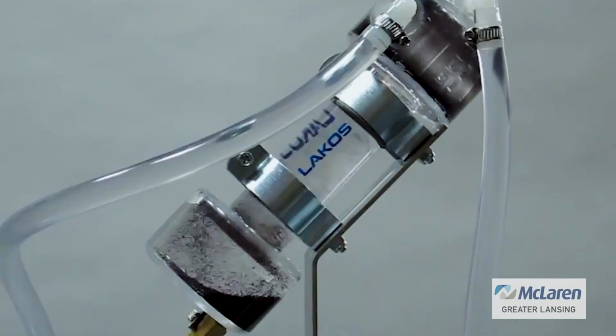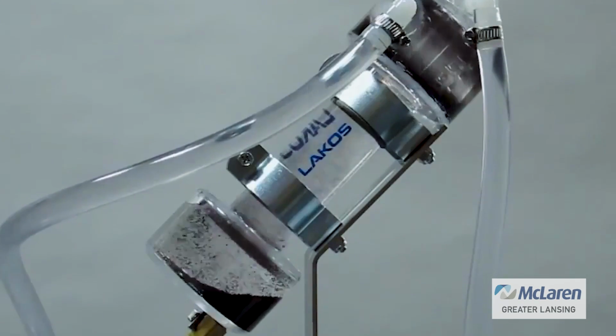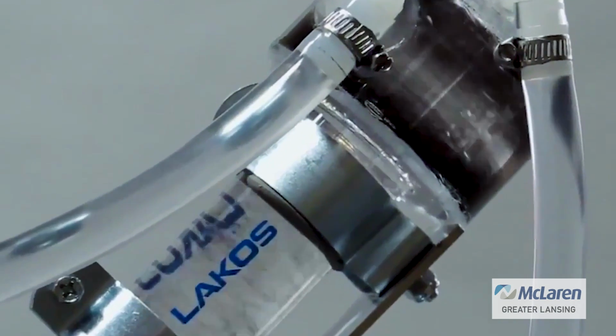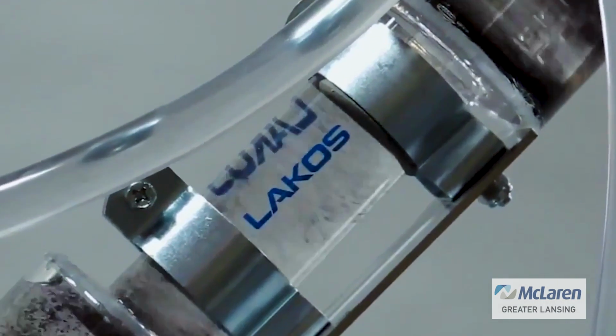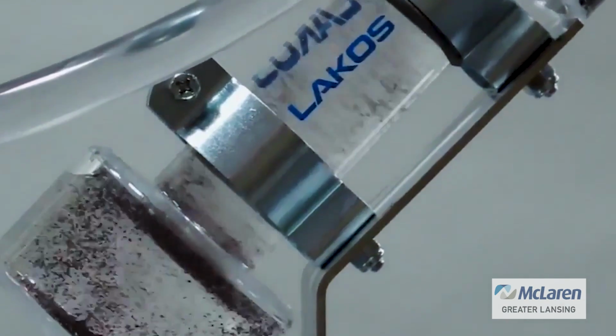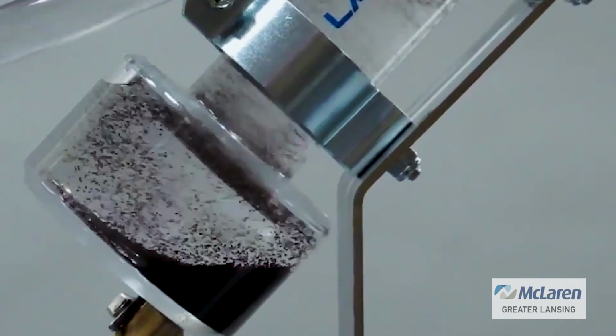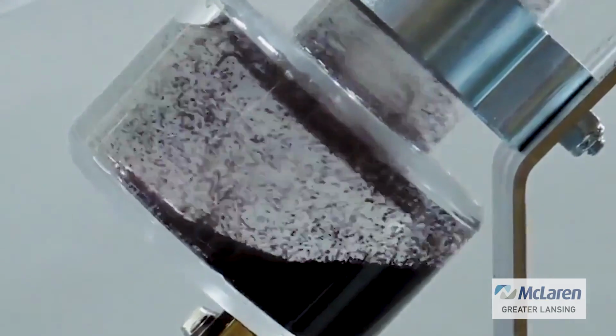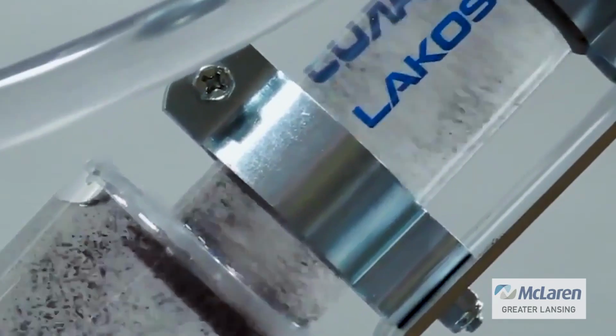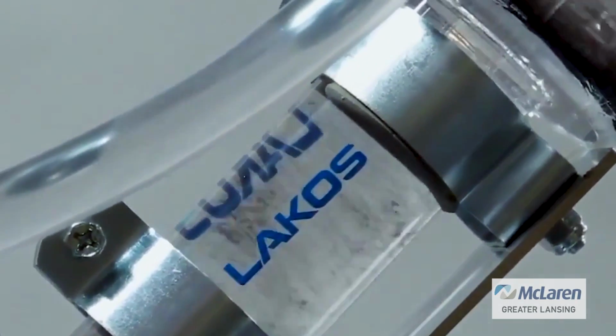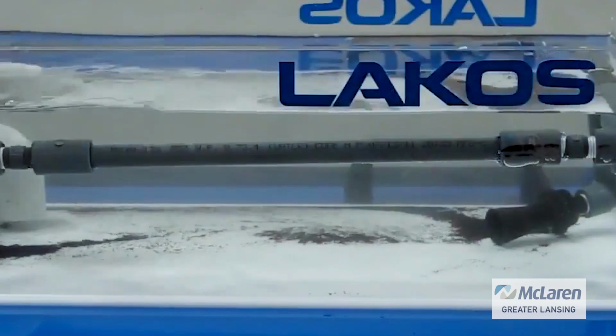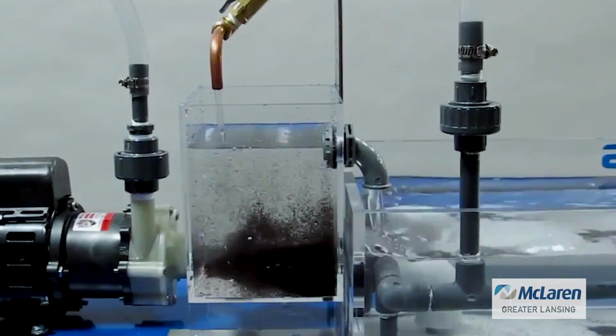Have we had owner training with the water treater yet? They have a process as part of the water treatment that periodically they do a blowdown. They get rid of some water and make it up with clean water, keeping the concentration of dissolved solids under control. If that gets out of control, you look at the outboard face of the cooling tower, the fill material, and that's where you start having those dissolved solids drop out of suspension, right? You guys won't see that probably, but in older towers where the water treater hasn't done it, or the owner maybe has said, we don't want to blow down to the degree that you think we need to, you could find that. That's time to call Du Bois, whoever is out doing your water treatment.